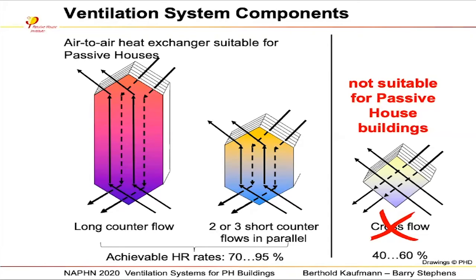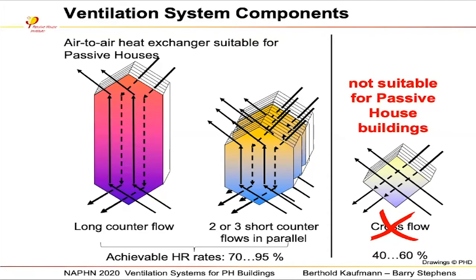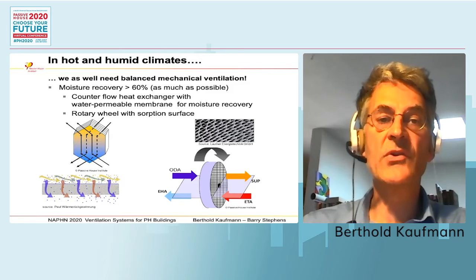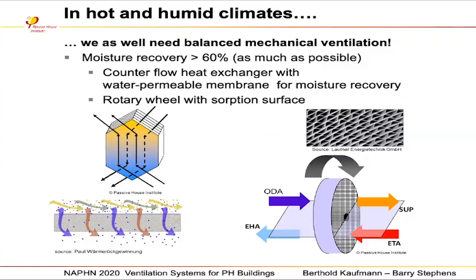Well, one thing is this 75 or even more heat recovery, you will only be able to reach with a large counterflow heat exchanger. And you see here on the left-hand side, a very large one. In the middle, this is a shorter one. This is the strategy people go for nowadays. And you see you can do it deeper to reach the same level of heat recovery. What you should never do for passive house and for an energy efficient ventilation system is these cross-flow heat exchangers. Well, this might be very small, but it's not suitable. It's too few, and you will need more electricity for the fans than you can save in energy during wintertime. The other option, as Barry mentioned before, is that you can go for ERV systems and heat exchangers, and this is on this slide.